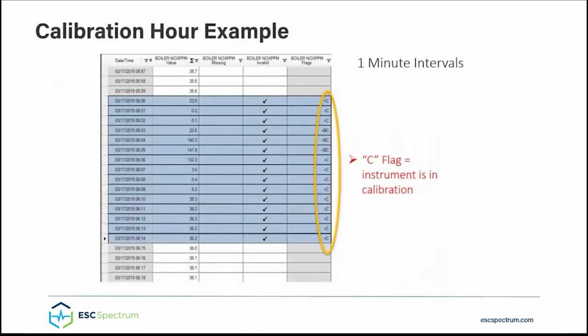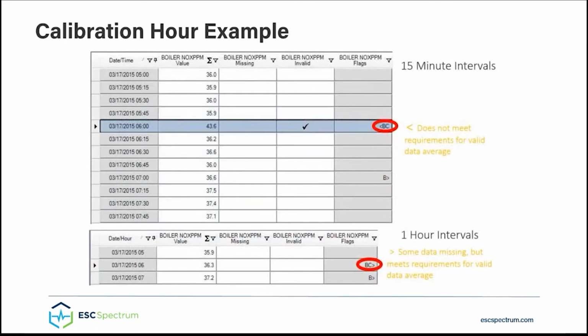Using StackVision's Data Lab, here's an example of what that might look like in your DAS. In Data Lab, the C flag means the analyzer was in calibration, and the less than symbol means the interval was not valid. Here we can see that the calibration started at the start of hour 6 and ended at 6:15. Moving to the 15-minute interval, we can see again that the 6 to 6:15 interval was in calibration and therefore not valid.